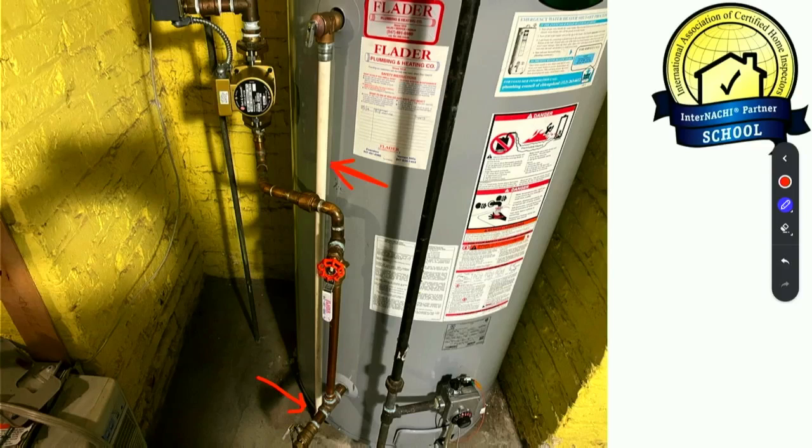So I mean, I don't know what I'm going to tell somebody because they sell these things at Home Depot and everybody's putting them on there. And I don't think the water heater cops are coming to arrest anybody. But I know that some plumber's going to walk in here 3 weeks later and he's going to say, well, it's going to be $150 to put in a new temperature pressure relief discharge tube because it's got to be metallic, and your home inspector should have told you that. So send him the bill. He'll pay us. And I'm like, well, thank you. But so we just make a comment of them and let people know, but it's their choice.